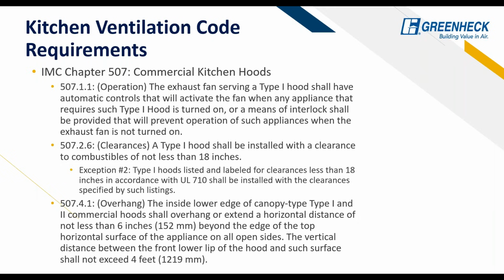Okay, so some quick code highlights. I'm not going to go through all of these. Just to reiterate what we're looking at with the hood and what the requirements are when you're sizing a hood, first and foremost is the operation. A type 1 hood must have automatic interlock with an exhaust fan. What that means is that if they start cooking without actively turning on a switch or anything like that, the fan still needs to automatically operate. That's done with the temperature sensor inside the hood, and it also compares it with the temperature sensor in the room. Once it senses a rise of temperature inside the hood, it'll automatically turn on the fan.